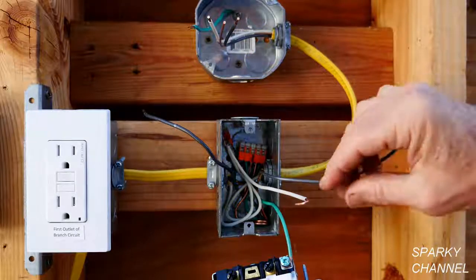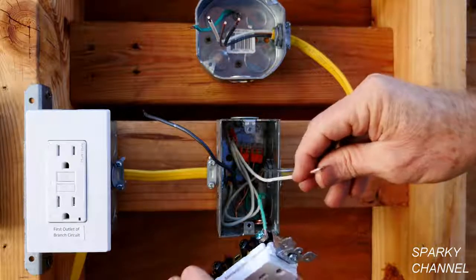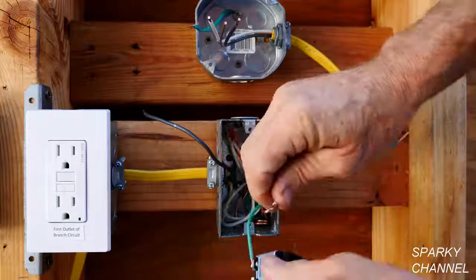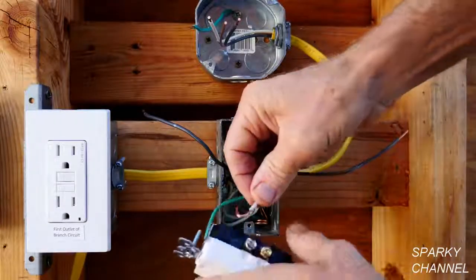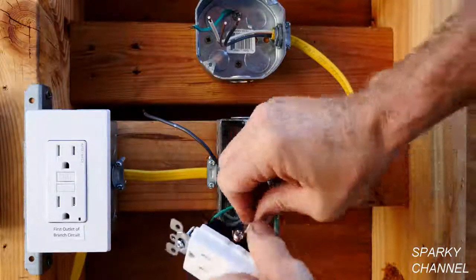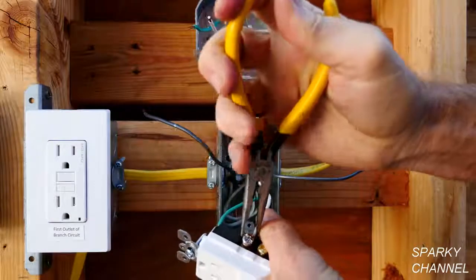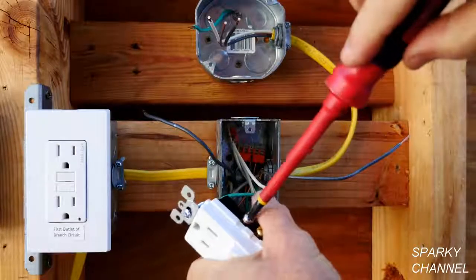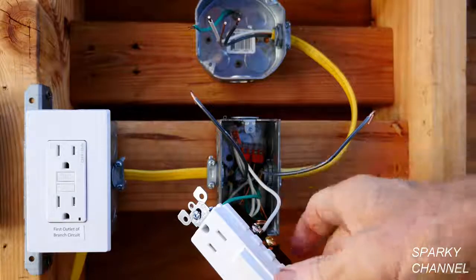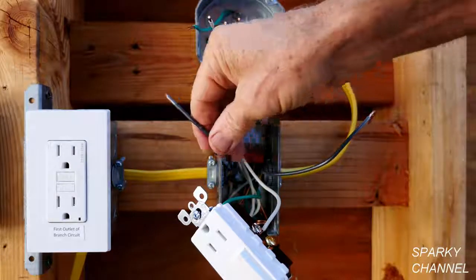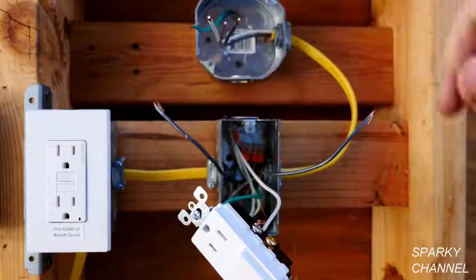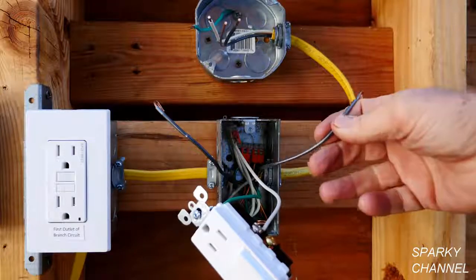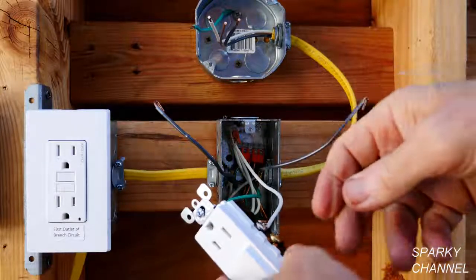Now put the neutrals back into the back of the box, and we're going to take the neutral and put it around the silver terminal in a clockwise manner, crimp it, and tighten it down securely. Okay, now we're going to hook up the hot wires. Remember, this is the line wire coming into the box. This is the load wire leaving the box going to the light.